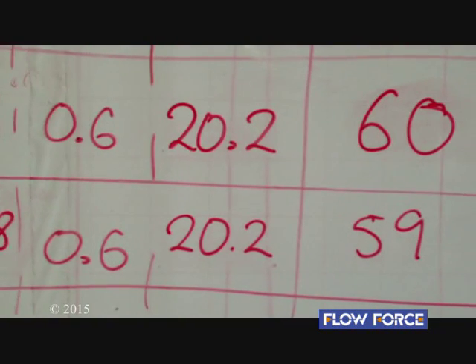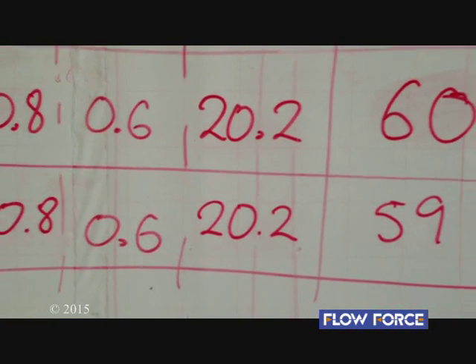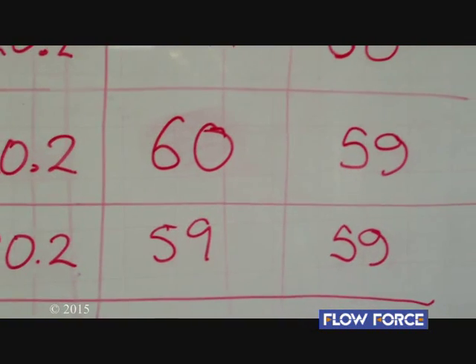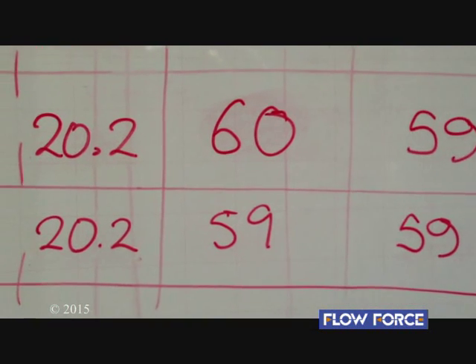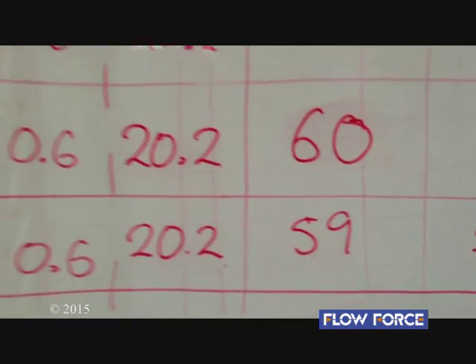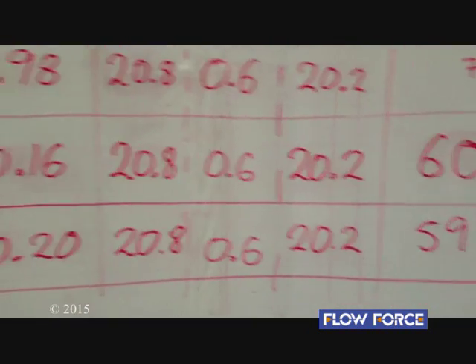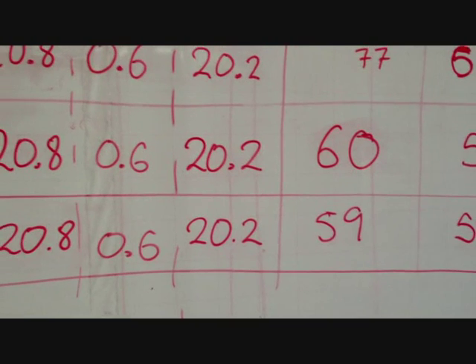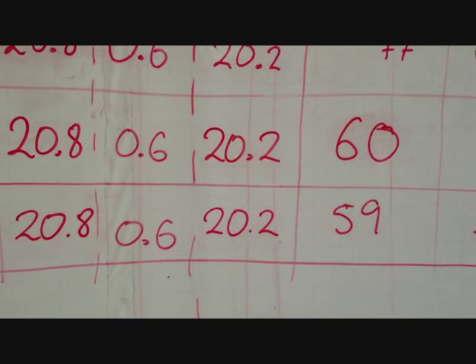so our actual weight was 20.2, which means that our calibration from previously with a Calcon 59 will stay the same. We would probably run one or two more tests at this to prove that we were close, but looking at this, we'd say the machine is calibrated.